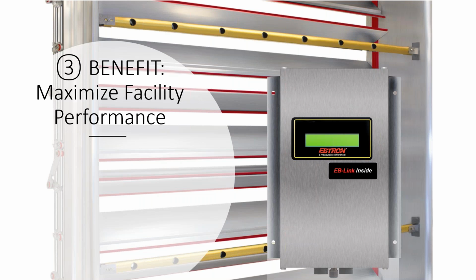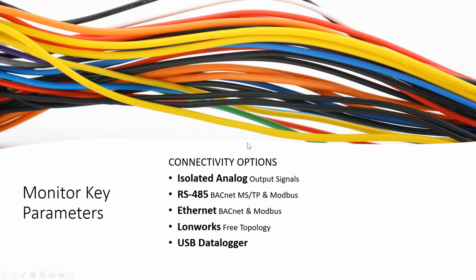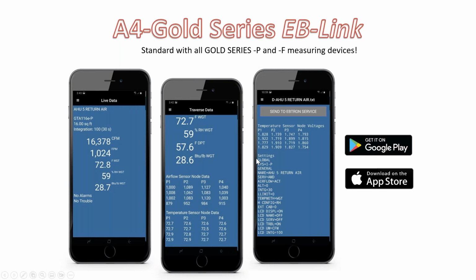So airflow is a really important indicator for facilities managers. And what you really want to do is use an airflow station on your supply, on your return, on your outside air to diagnose any problems. And obviously, again, demonstrate you're providing the right amount of outside air to the space. We also have an EBLink tool, which facilities managers love, which controls contractors love, and also engineers really like as well. Because you can see everything in live time of what's going on at the EBTRON unit.